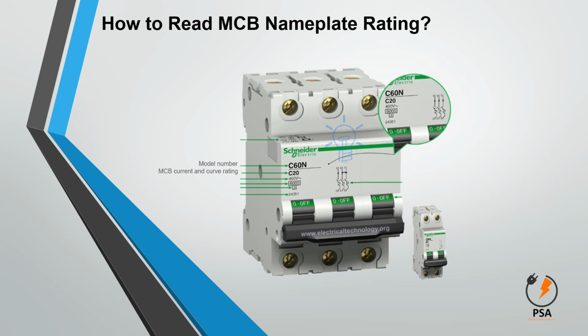On a resistive load, say a heater or normal lighting load, it will be the B curve. For an inductive load, like pumps, motors, etc., it will be the C curve, and for a highly inductive or capacitive load, it will be the D curve. The numeral part indicates the rating of the MCB in amperes. In the given example, it is 20A. The MCB rating is very important, and be very precise about it.